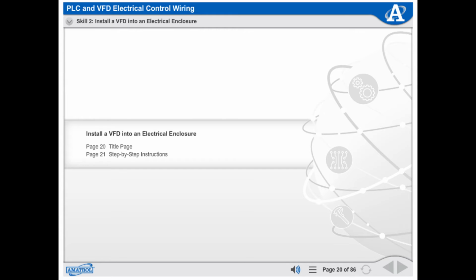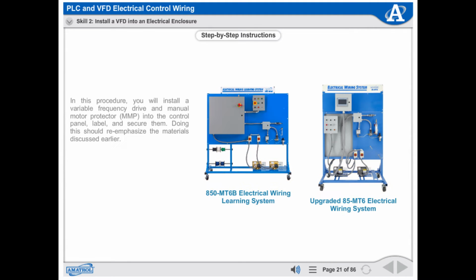Install a variable frequency drive into an electrical enclosure. In this procedure, you will install a variable frequency drive and manual motor protector into the control panel, label and secure them. Doing this should re-emphasize the materials discussed earlier. Click on the equipment to view the step-by-step instructions for performing this procedure using the selected system.